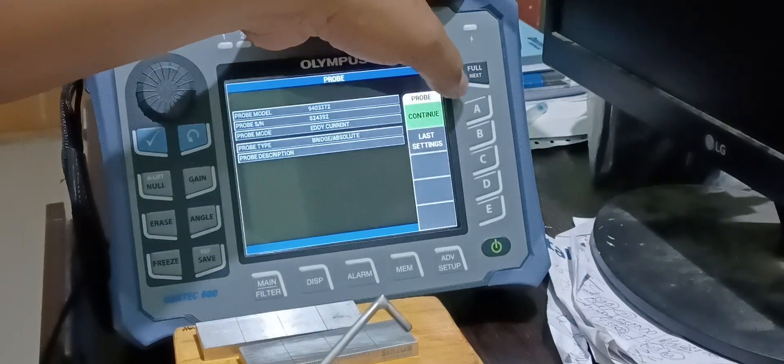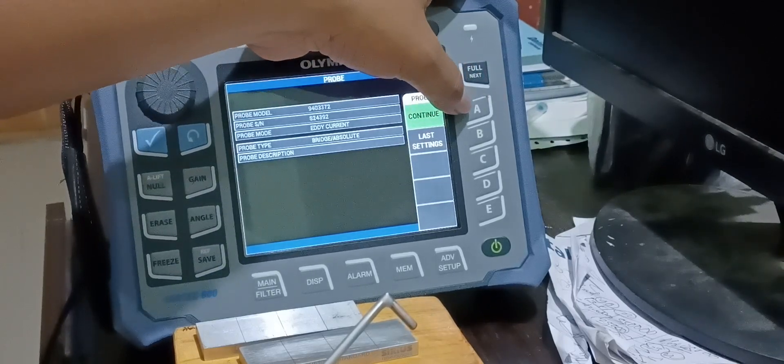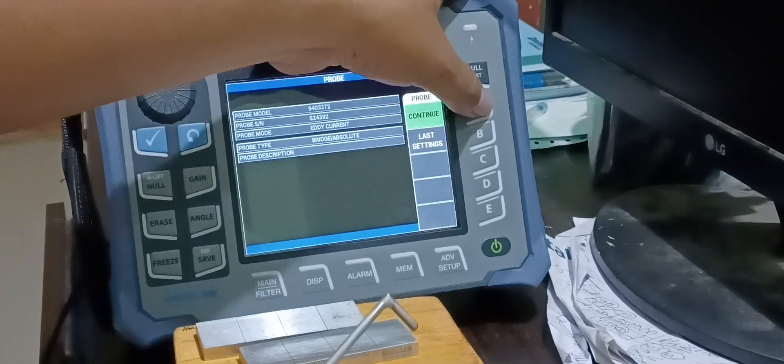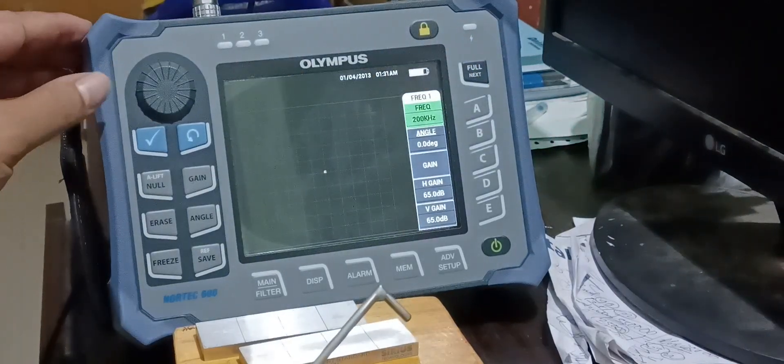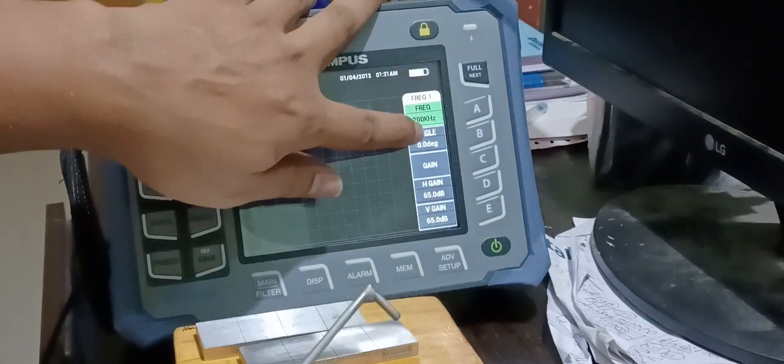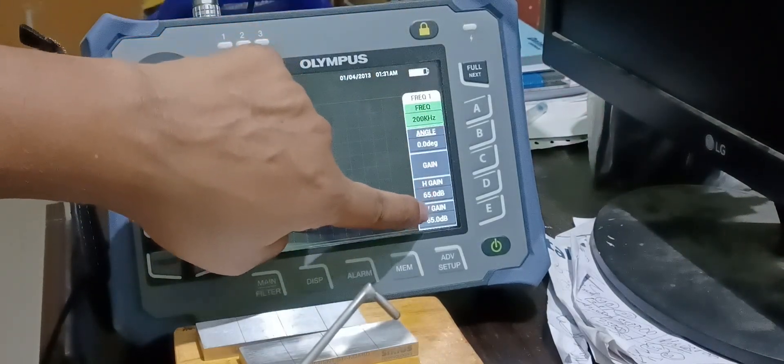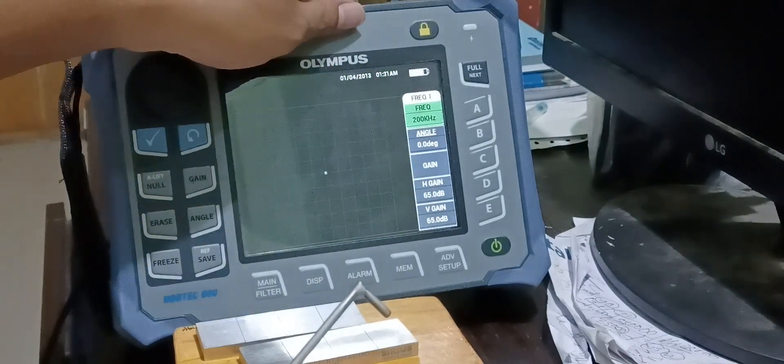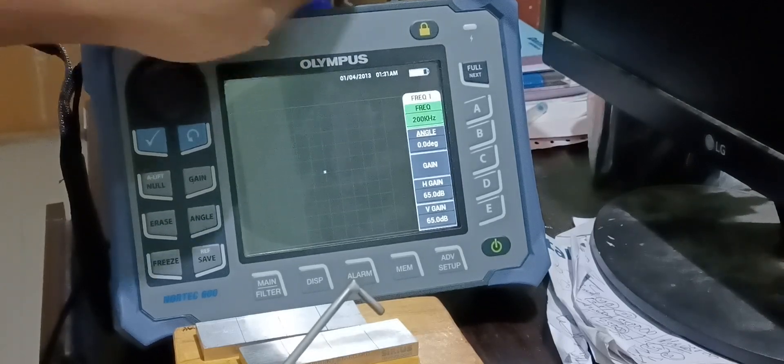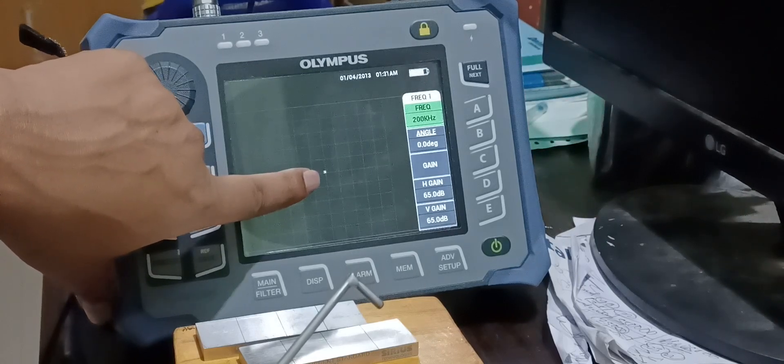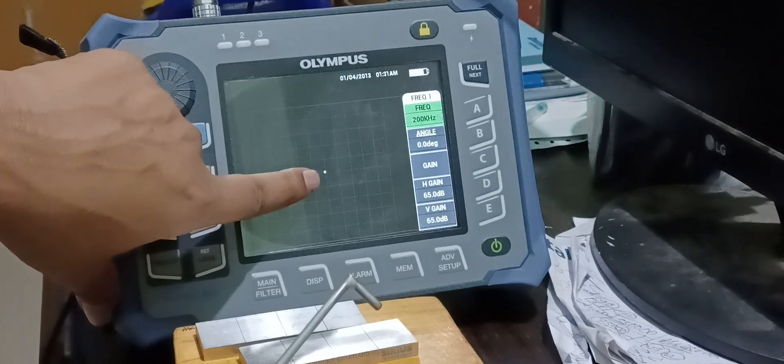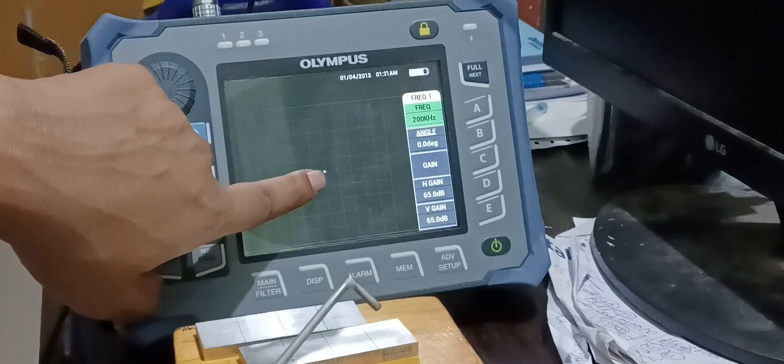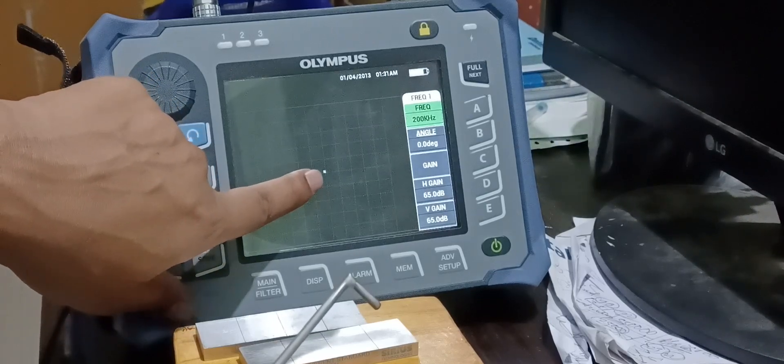For example, if I press A this continue option will get activated. I am pressing A now. Now it is showing me an impedance plane. In this impedance plane, you can see the frequency, the angle, the gain, the horizontal and vertical gain. Everything is now starting to appear on the screen. Now this is the null point. Here you can say it's an air point and null point. It is now the net available impedance of the coil. And you can preset this null point as per your convenience. Now it is right in the center of the machine.